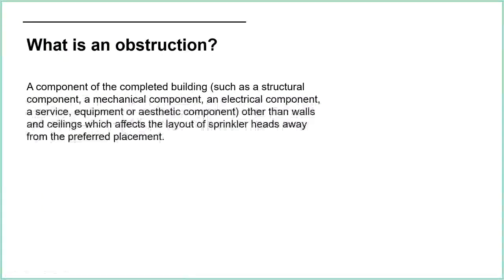First of all, we need to look at what an obstruction is. My own definition: an obstruction is basically anything which isn't a ceiling or a wall which is getting in the way of sprinkler head placement — a component of the completed building such as a structural, mechanical, electrical, service equipment, or aesthetic component, other than standard walls and ceilings, which affects the layout of sprinkler heads away from their preferred placement.